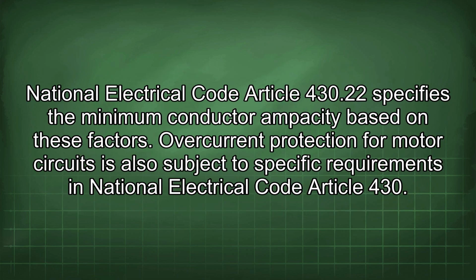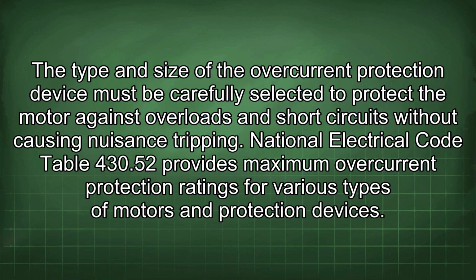National Electrical Code Article 430.22 specifies the minimum conductor ampacity based on these factors. Overcurrent protection for motor circuits is also subject to specific requirements in National Electrical Code Article 430. The type and size of the overcurrent protection device must be carefully selected to protect the motor against overloads and short circuits without causing nuisance tripping. National Electrical Code Table 430.52 provides maximum overcurrent protection ratings for various types of motors and protection devices.